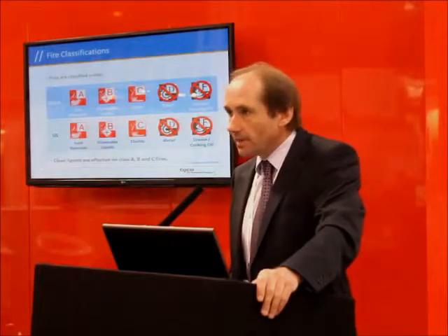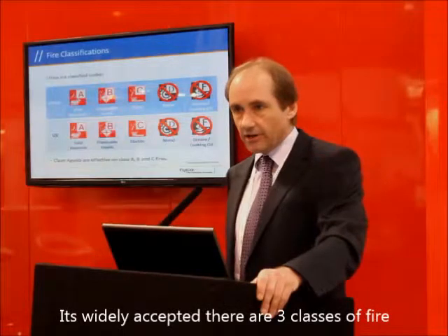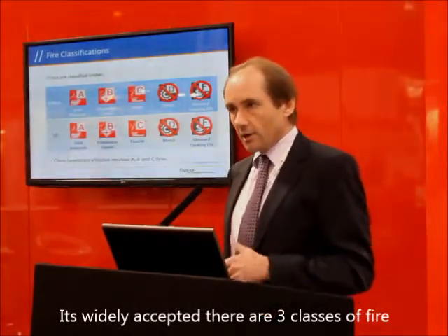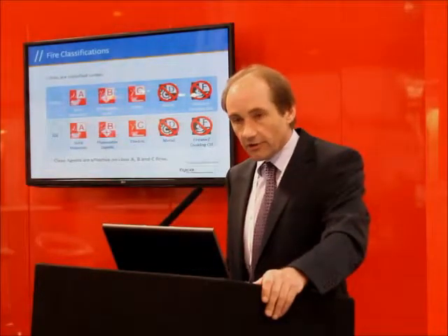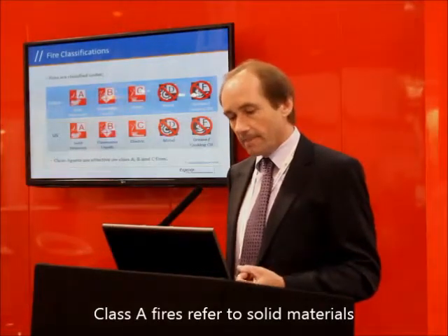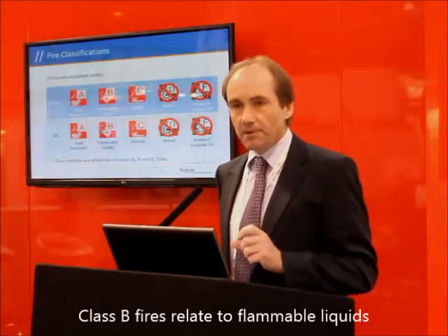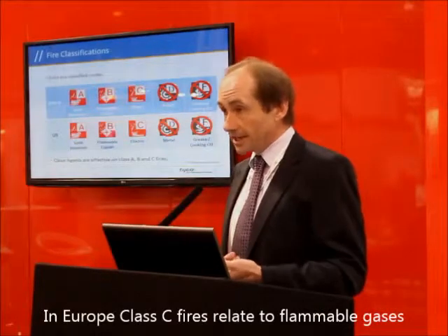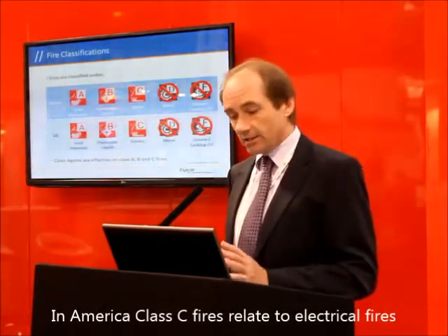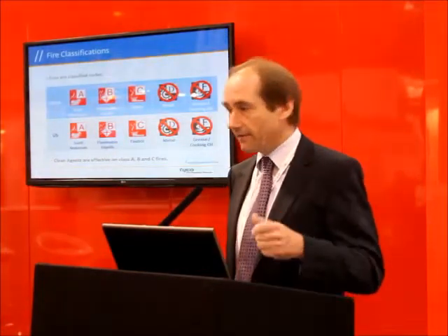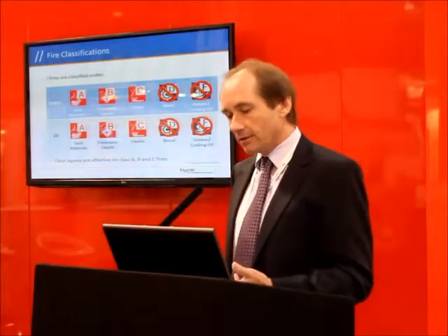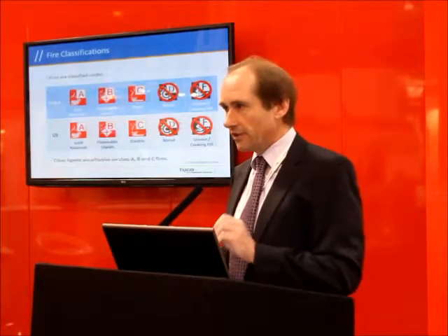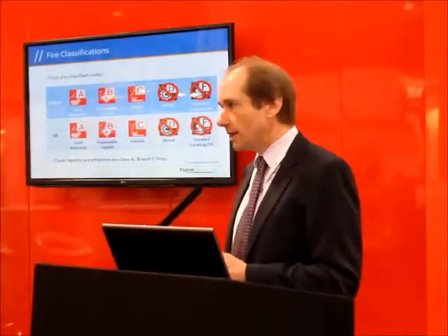Generally, when we look at clean agents and to a large degree with CO2 as well, we're looking at three classes of fires: Class A, B, and C. The terminology differs between the European market and the US. A Class A fire globally is a solid burning fire, Class B is a flammable liquid. Class C in European terminology is flammable gases, whereas in the US it typically refers to energised or electrical type fires. These products typically wouldn't be used on reactive metals, grease, or cooking oil, so you wouldn't see them in kitchen environments or industrial processes with reactive metals.